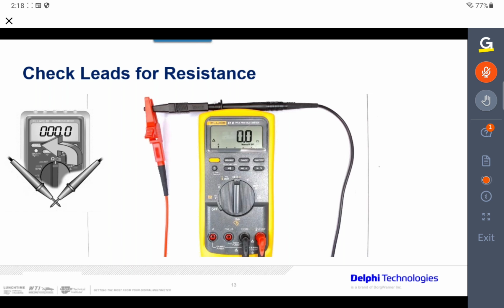It'll save you time. We had a meter in a class recently, and a student was bringing this up for me a little after the first class, and his meter read 100 ohms. That means that he would have affected my circuit and had a problem. So we checked that one out. Again, 0.1, 0.2, okay. Anything above 0.2, the leads need to be replaced.